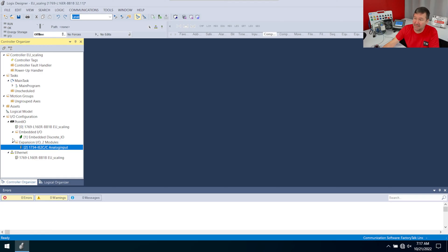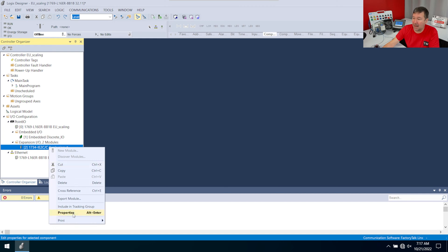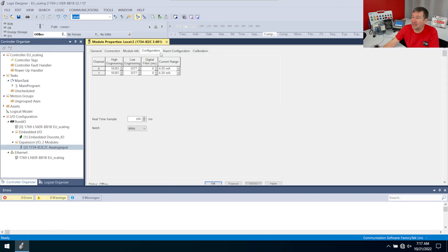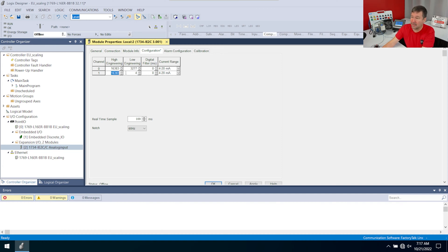In Studio 5000, I have a 1734 IE2C, and if I right-click and go to Properties, then on the Configuration tab, we have our high and low engineering units. And what several of you have said is if you want 4 to 20 milliamps scaling, all you need to do is put 4 and 20 milliamps into here.